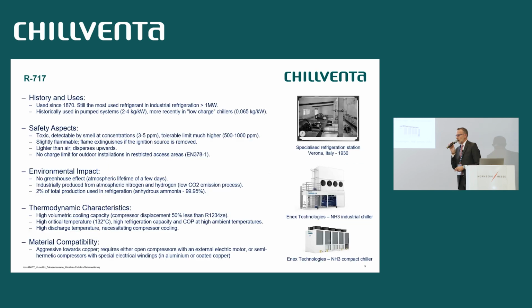So let's talk about ammonia. For those of you who are not familiar, ammonia has been used since the 19th century. It's still one of the most used refrigerants in industrial refrigeration, especially for large systems above 1 megawatt. It's been historically used in pumped systems, so the ammonia is circulated by a pump towards the users. These systems have a very large refrigerant charge, up to 4 kilograms per kilowatt. So you can have thousands of kilos of refrigerant in these systems.